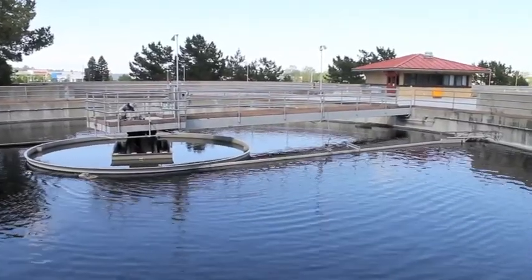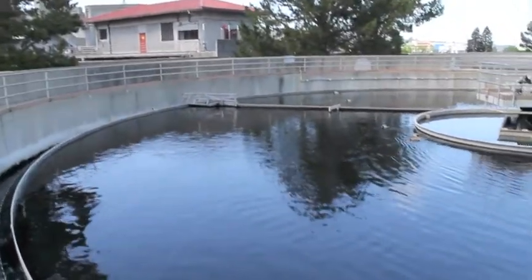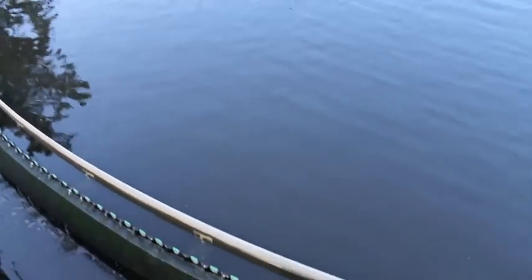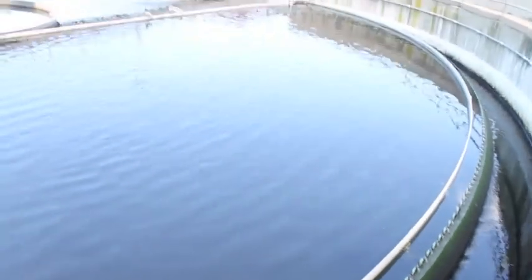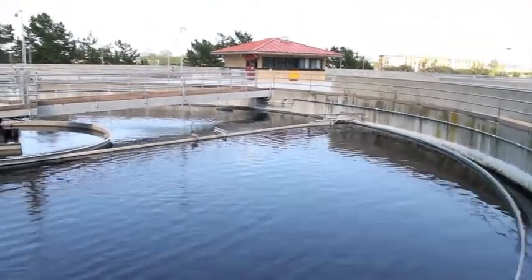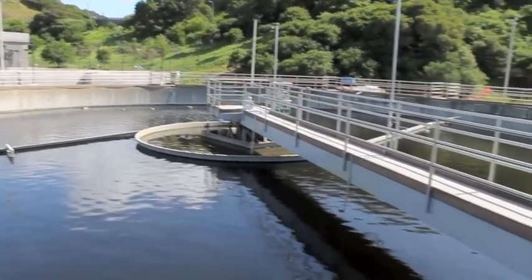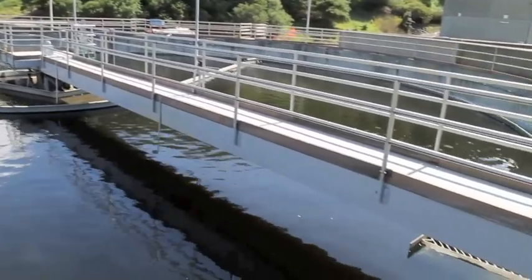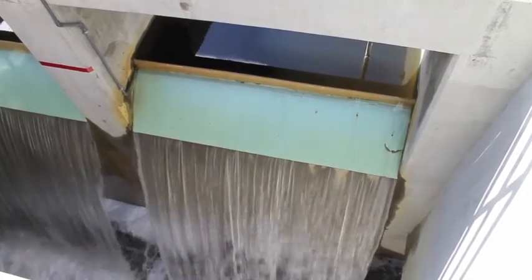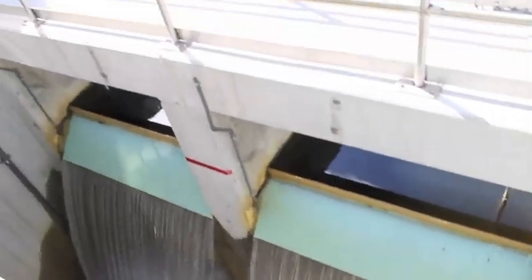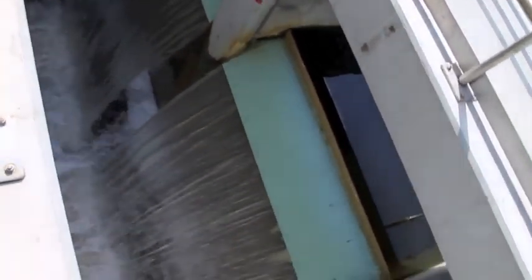When water enters the sewage treatment process, it can naturally be assumed to be contaminated with harmful bacteria, as is the nature of sewage. As such, it is essential to disinfect the water to remove potentially harmful bacteria that remain in it. In order to remove these harmful bacteria, the wastewater is disinfected with chlorine. Chlorine contact tanks release a computer-controlled dose of bleach to kill pathogens. Afterwards, the water is tested for chlorine levels and then subsequently dechlorinated before being pumped into the outfall pipe and into the bay.